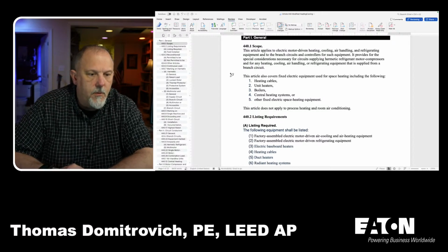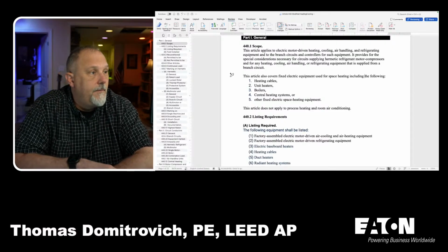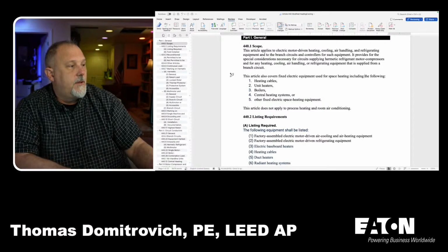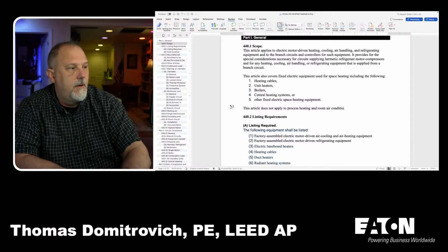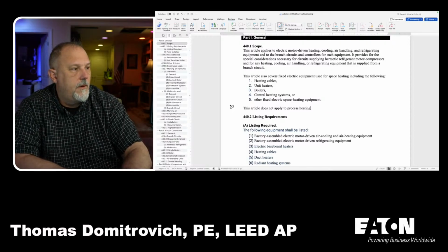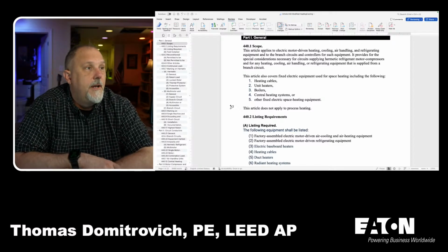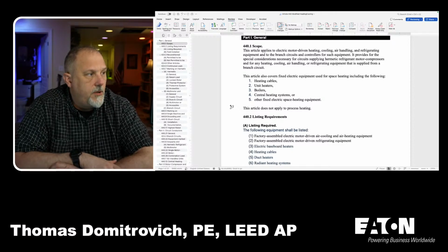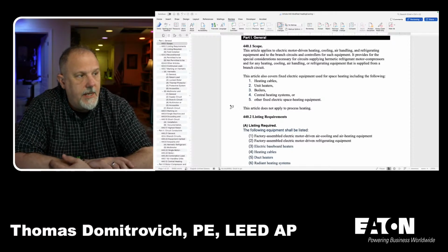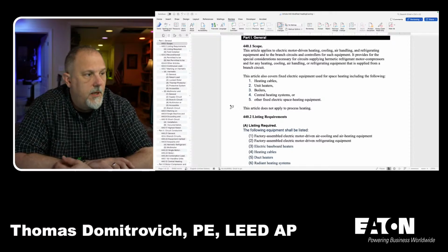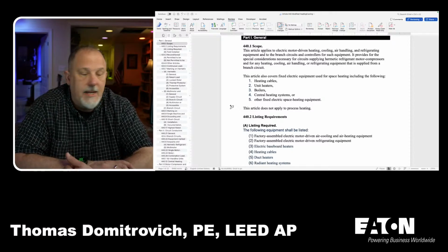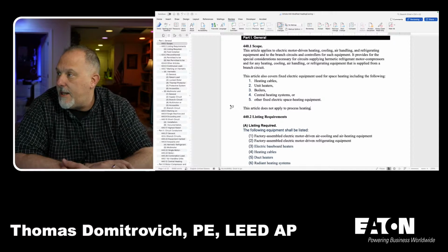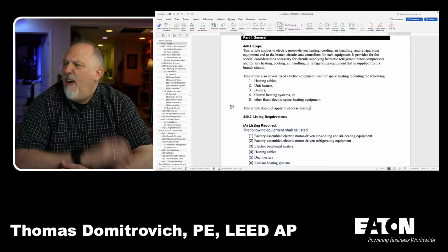Room ACs are in 440. See, I'm in 440. Okay, so I got to take that out. Good point. I'm in 440, so that would be it. All right, so this article also covers fixed electric equipment used for space heating, including the following: heating cables, unit heaters, boilers, central. This article does not apply to process heating because process heating would be 425. Right?